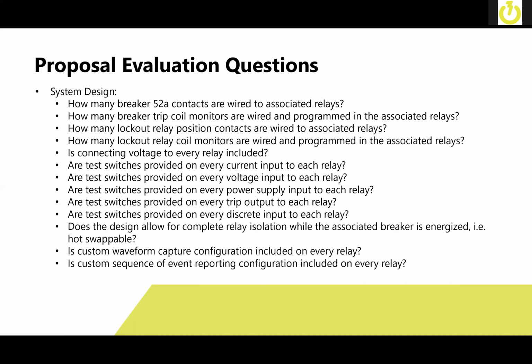And then one question that we get frequently asked is, does the system design allow for complete relay isolation while the associated breaker is energized? For instance, you have a motor that the relay goes out on, and that motor may be an integral process in your facility. Do you want to have the option to be able to pull the relay, send it to the manufacturer in the event of an issue, and still keep your motor running and still keep your process running? Does it allow you to perform maintenance while that equipment's running?